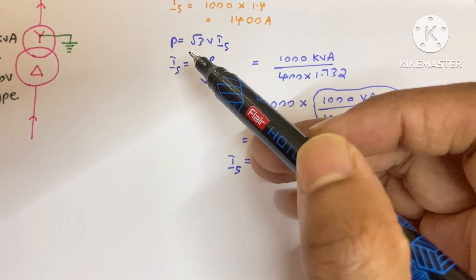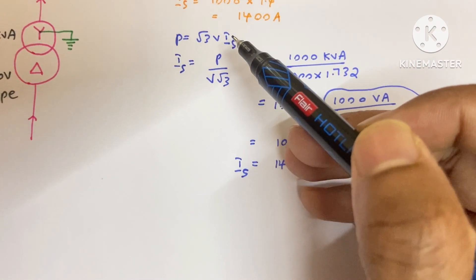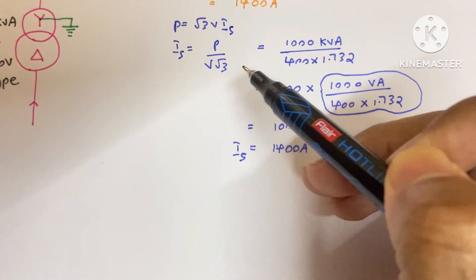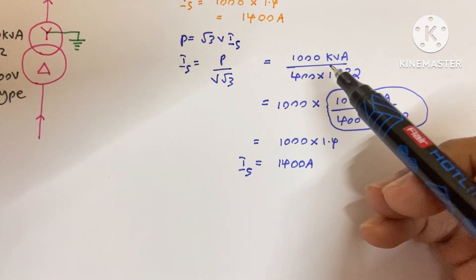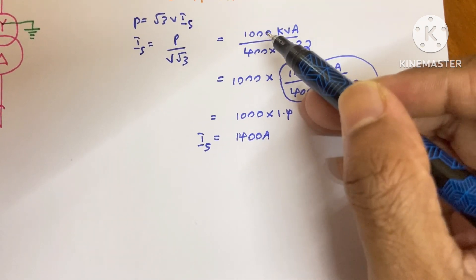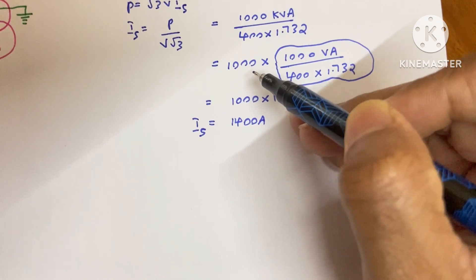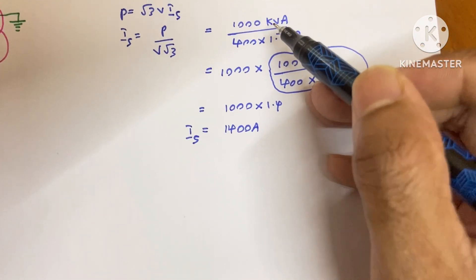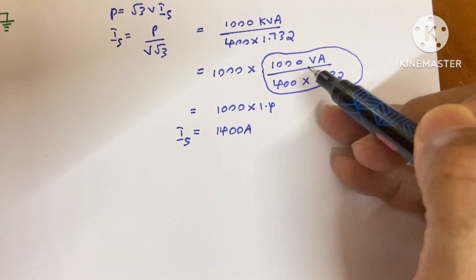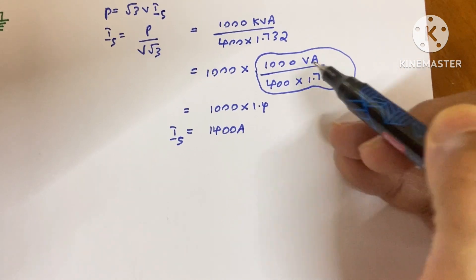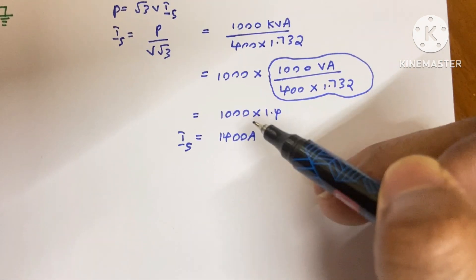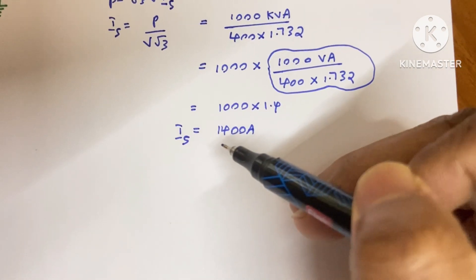We know that the three-phase power equation is P = √3 × V × I. So Is = P / (V × √3) = 1000 kVA / (400 × 1.732). Here the kVA is converted to VA by multiplying by 1000, and when we calculate 1000 / (400 × 1.732) we get 1.4. That means 1000 multiplied by 1.4 gives 1400 A.